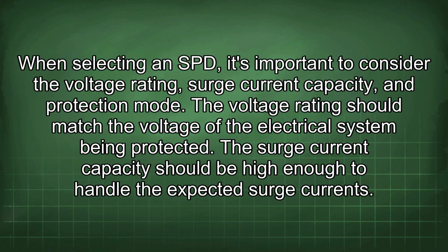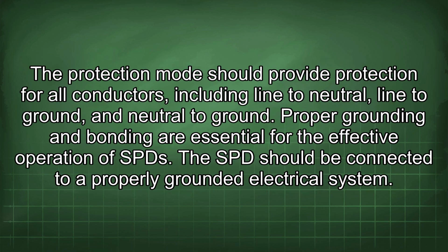When selecting an SPD, it's important to consider the voltage rating, surge current capacity, and protection mode. The voltage rating should match the voltage of the electrical system being protected. The surge current capacity should be high enough to handle the expected surge currents. The protection mode should provide protection for all conductors, including line to neutral, line to ground, and neutral to ground.